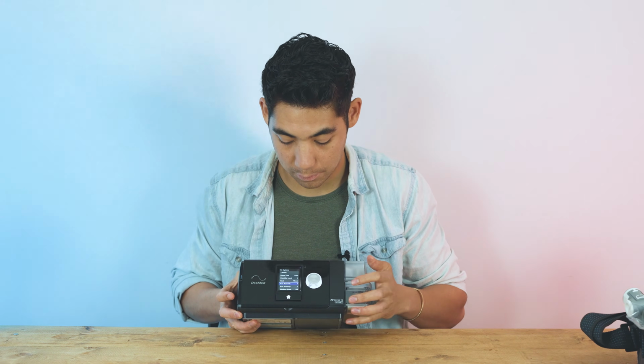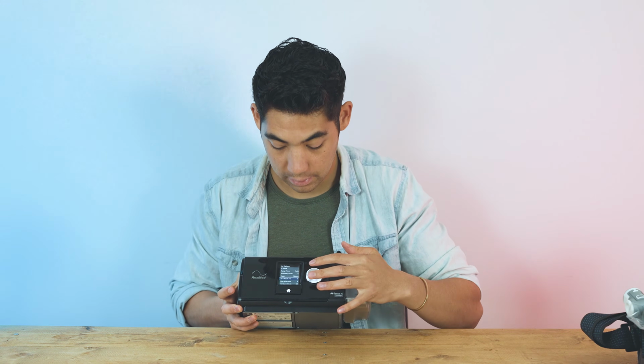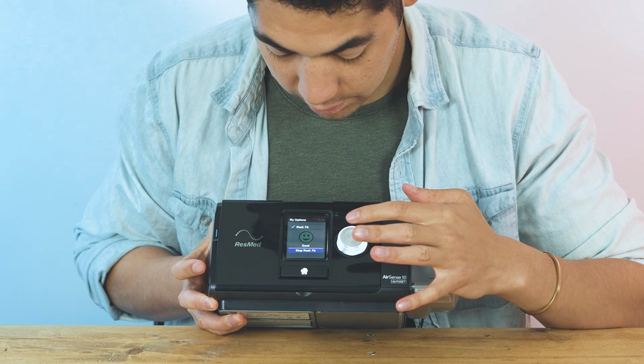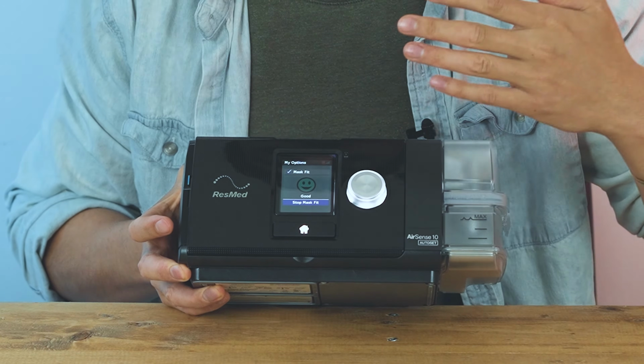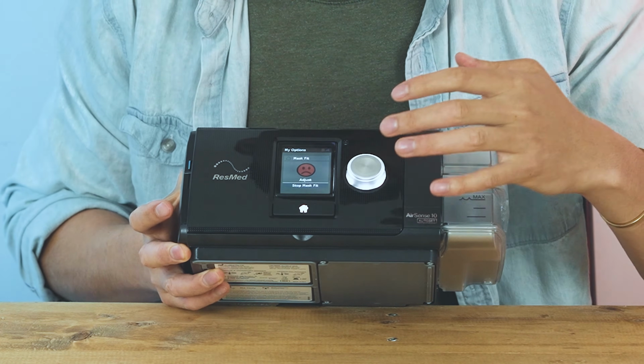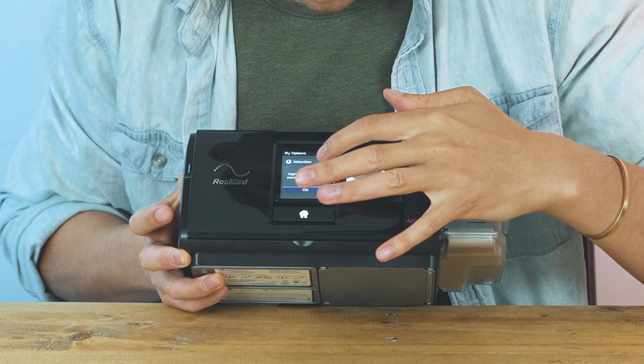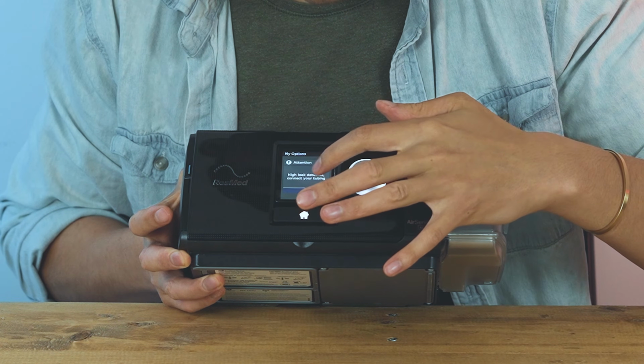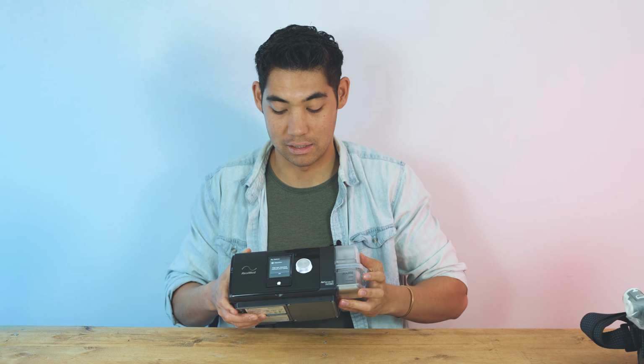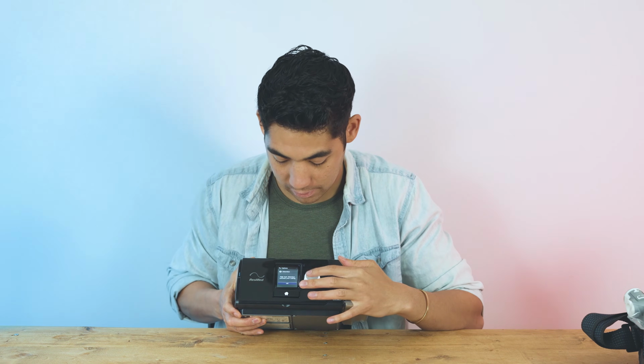So let's click that and see what happens. We don't have anything connected, so let's see. So run mask fit. It says startup mask, it's good, and it's blowing. And it says stop mask fit, high leak detected, connect your tubing. So obviously there's gonna be a huge leak if we do not have tubing or a mask, and that makes sense. So make sure to run that test there.